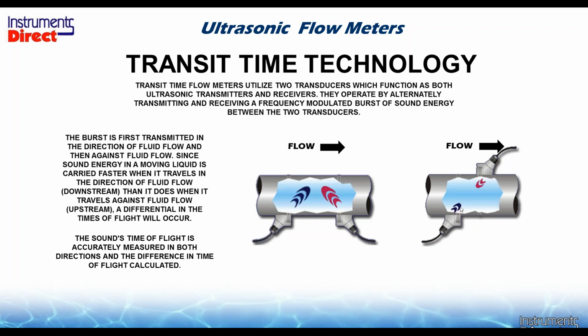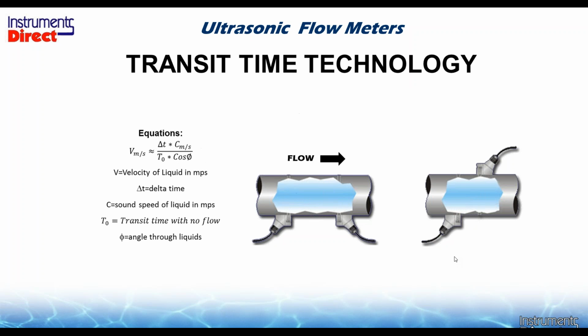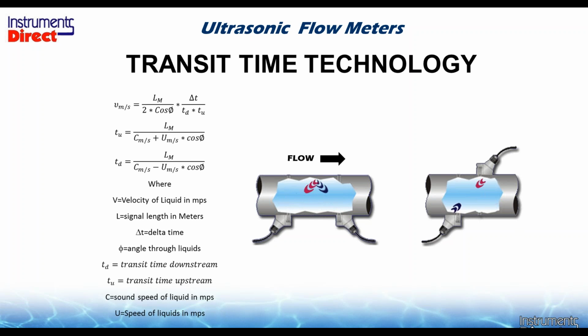So we usually use it on 24 inches and larger, or on nasty applications that are shorter. Now the math behind this equation is what's really been the core competency for many, many years, and we're going to show you a flow chart in a minute. But basically, we're looking at the differential time between the two signals to calculate your transit time. And what has evolved over the years, well, the core equation is the same, but we have more what-ifs and therefores. And so the technology has evolved dynamically in the last 30 or 40 years.